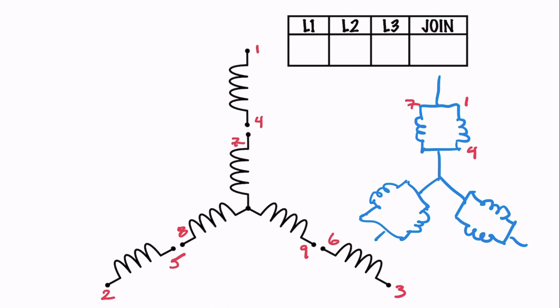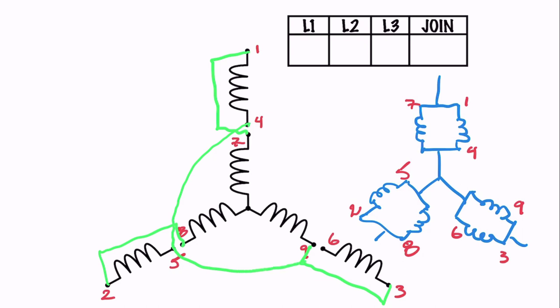Moving over to lead two — I've got two and five — and I'm going to connect two to eight, which then connects to the phantom lead. Then I've got three and six, and I'm going to connect that to nine and the other phantom lead. So this shows us that we're going to parallel one and seven, parallel two and eight, and parallel three and nine. We're also going to connect four, five, and six together.